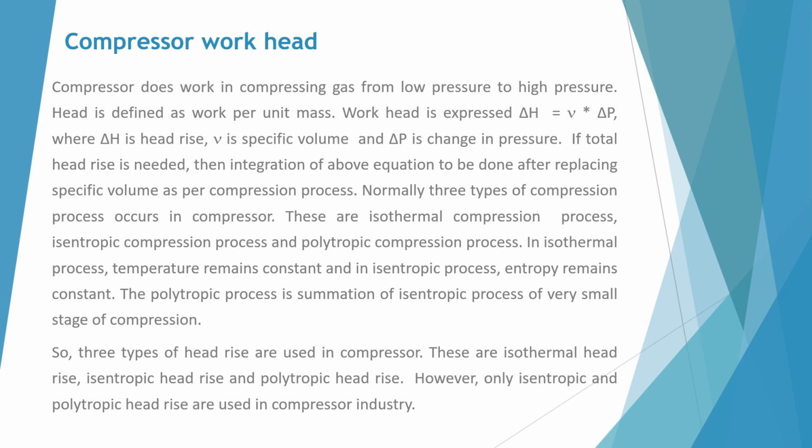Work head, compressor work head. Compressor does work in compressing gas from low pressure to high pressure. Head is defined as work per unit mass. Work head is expressed as delta H is equal to V into delta P, where delta H is the head rise, V is the specific volume, and delta P is change in pressure.